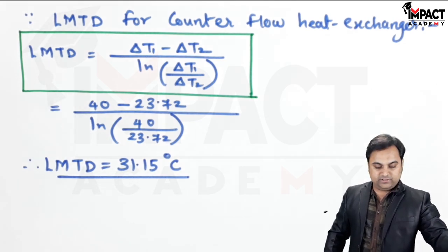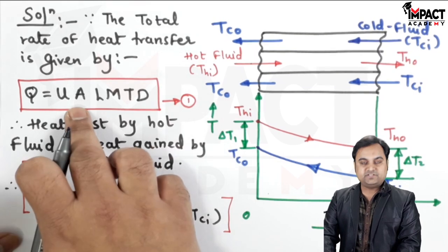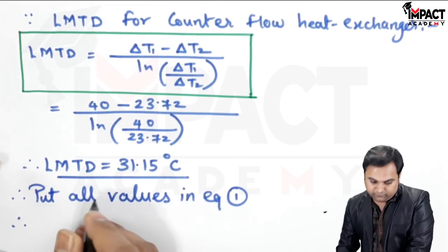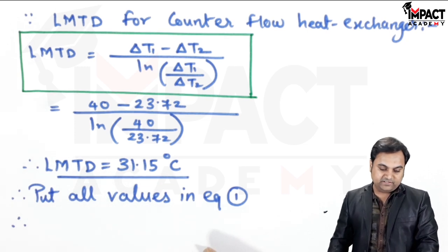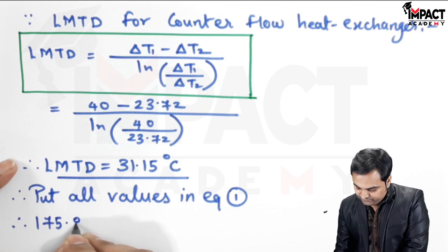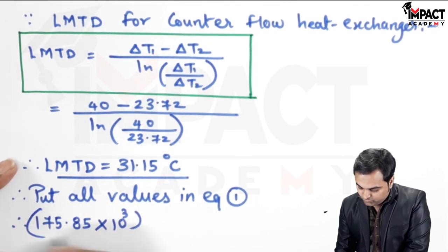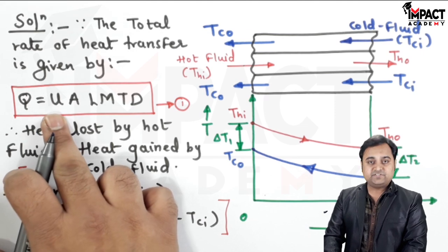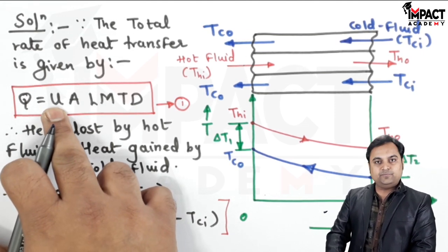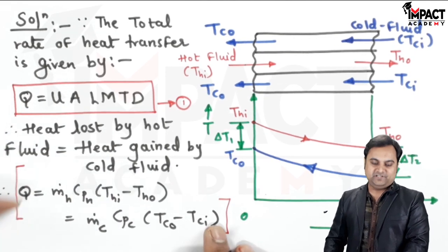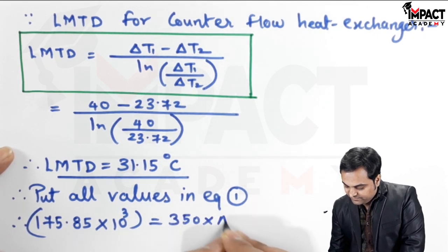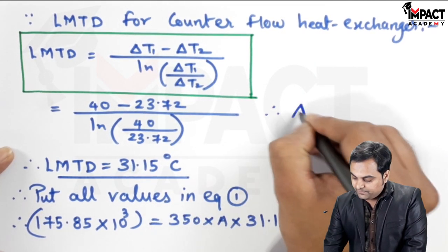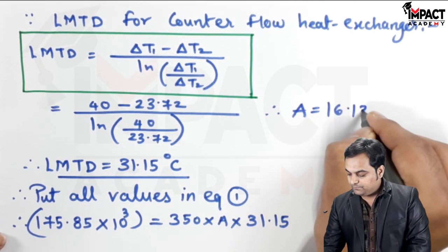The LMTD formula is: LMTD = (Delta T1 − Delta T2) / ln(Delta T1 / Delta T2) = (40 − 23.72) / ln(40 / 23.72) = 31.15°C. Substituting into Q = U·A·LMTD: 175.85 × 10³ = 350 × A × 31.15. Since U is in watts, Q must also be in watts. Solving gives surface area A = 16.13 m².